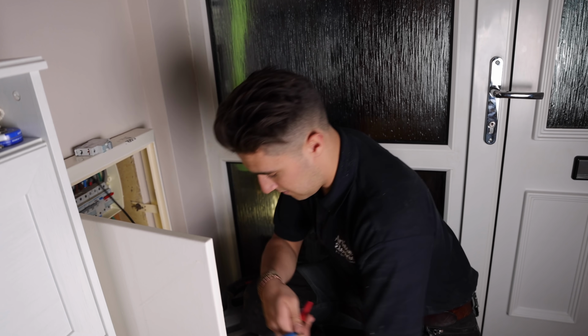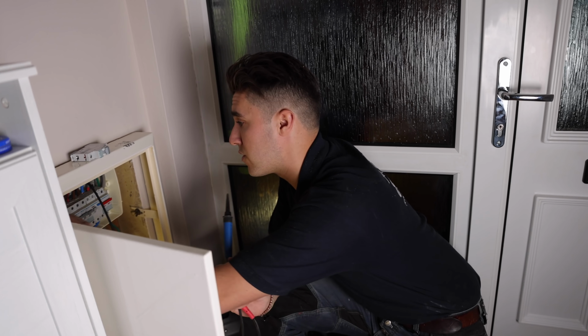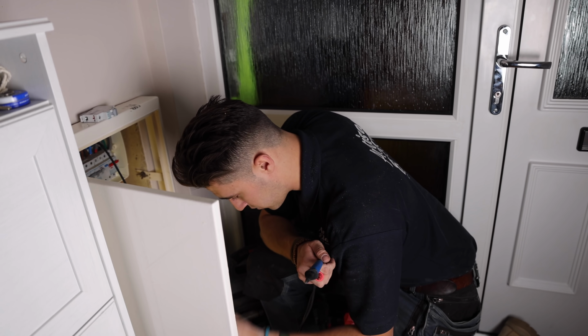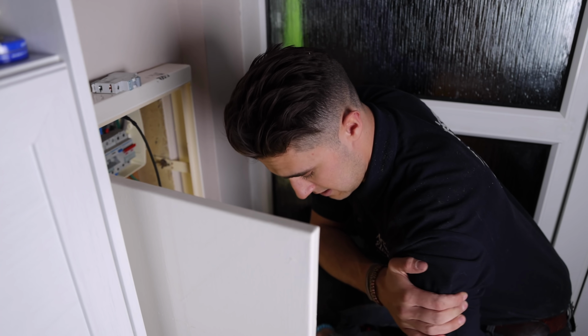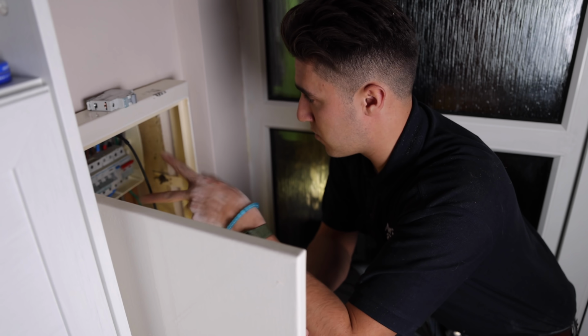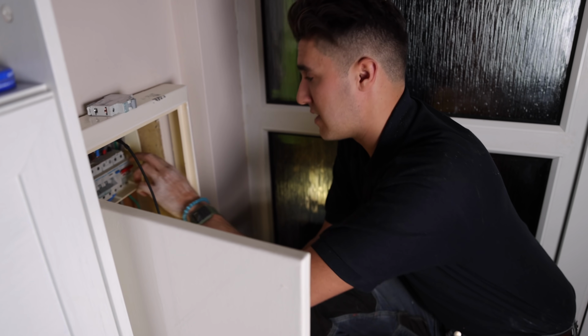Let's just test and see if we can get a ramp test on it, because it's holding with no load. But as soon as I switch any of the breakers on, even circuits we're not working on, boom, trip. Hager RCD at this time of night. Where am I going to get one? Maybe I'll try swapping them quickly, just to confirm that is what it is.